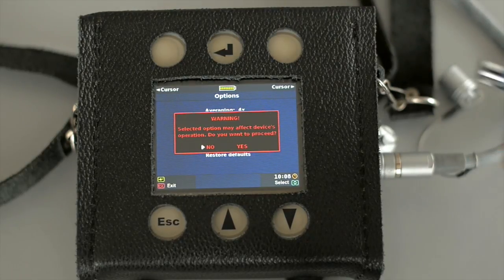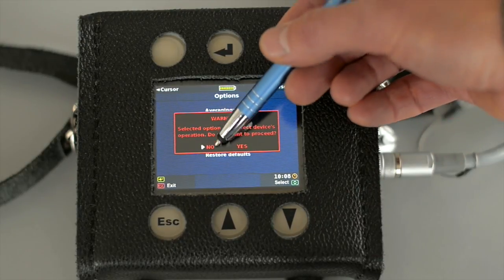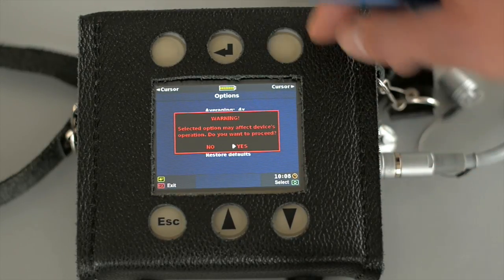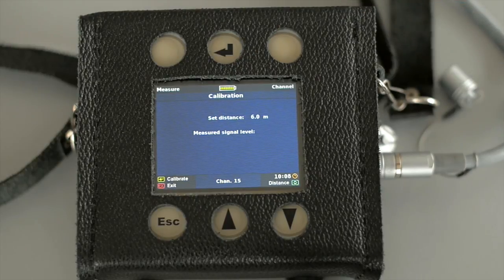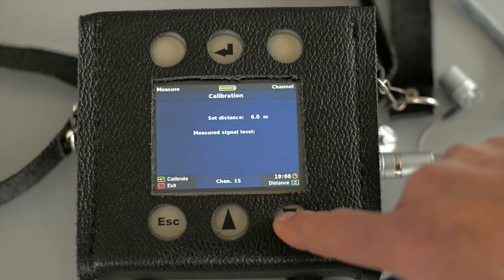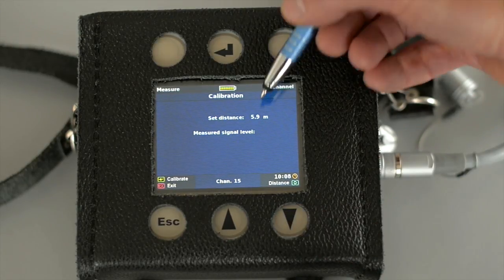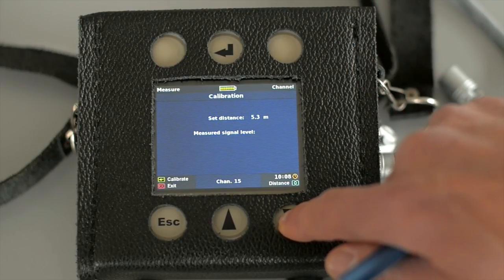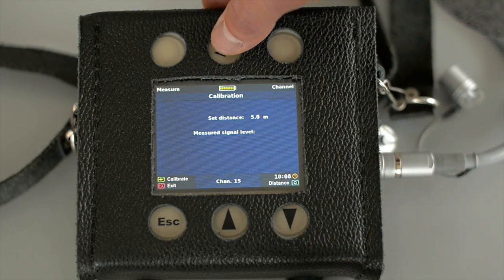When pressing the Enter key, we'll be asked to confirm the action because it may result in an unstable operation of the instrument when performed incorrectly. Now we can choose the calibration distance. We recommend using a distance from 4 meters to 6 meters. With this distance, the electromagnetic disturbance does not have much influence.